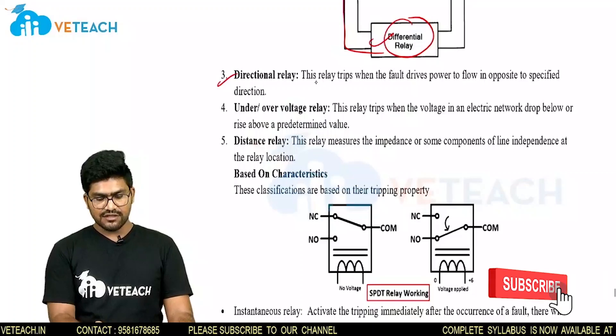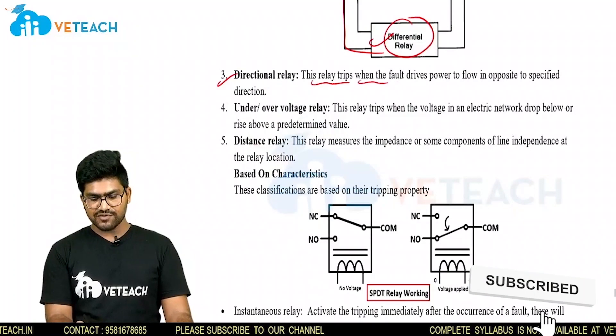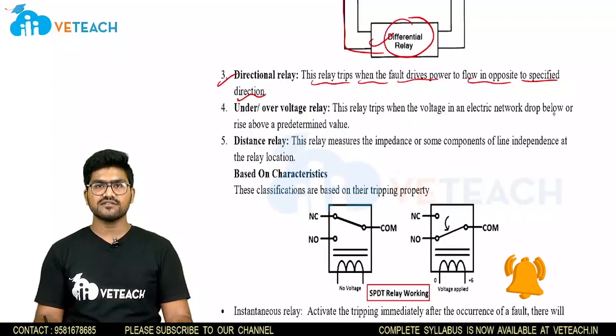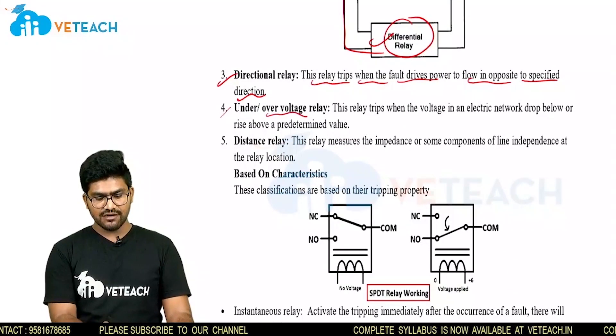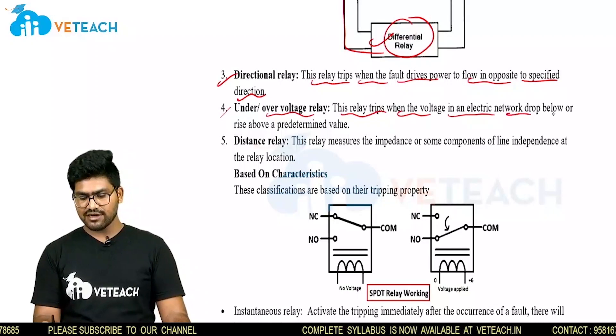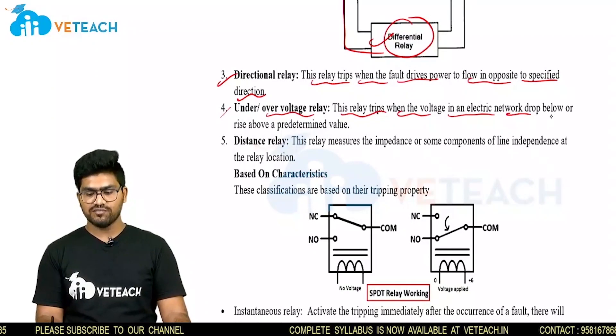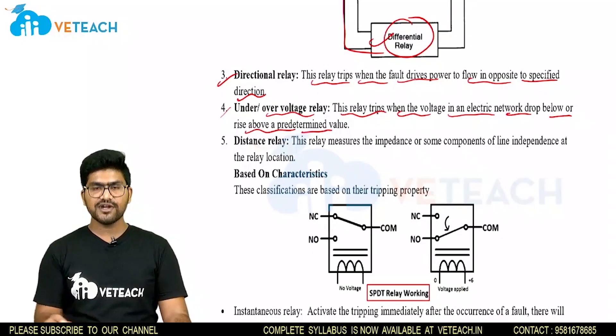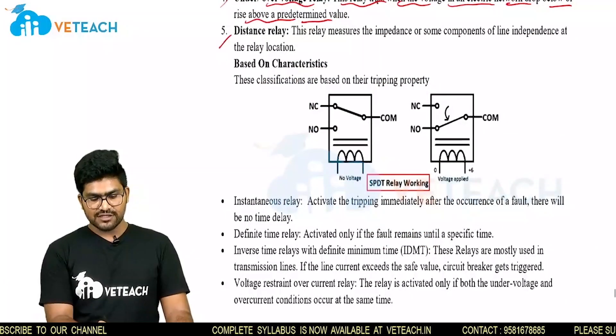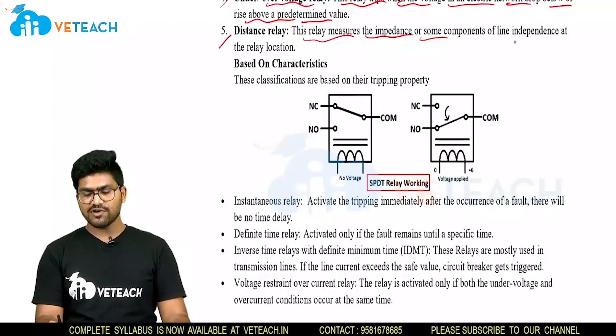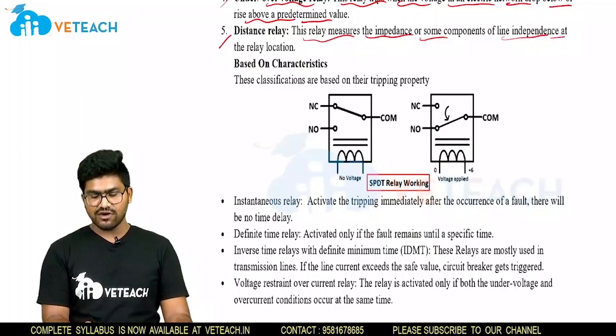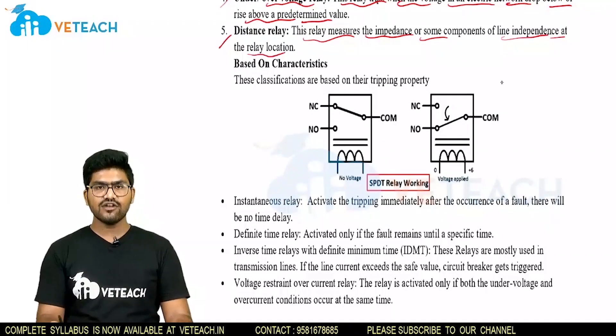Coming to directional relay — this relay trips when the fault drives power to flow in the opposite to specified direction. Next is under or over voltage relay. This relay trips when the voltage in an electrical network drops below or rises above a predetermined value. Coming to distance relay — this relay measures the impedance or some components of the line impedance at the relay location.